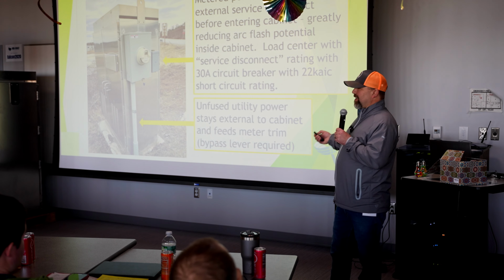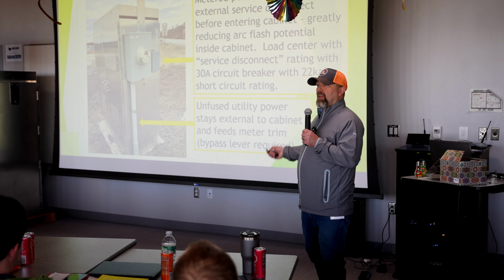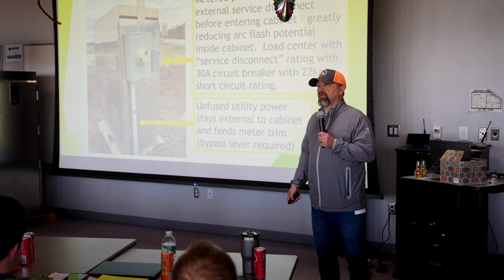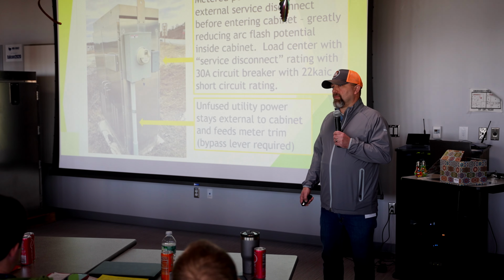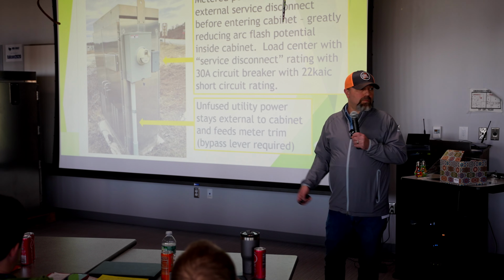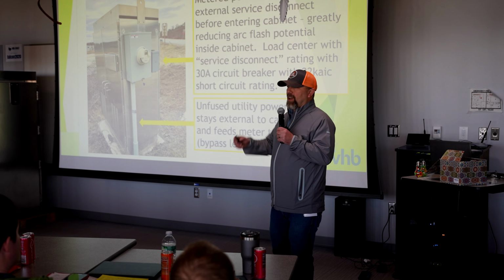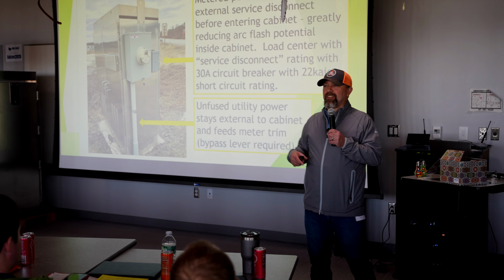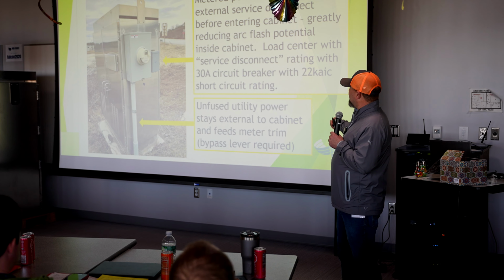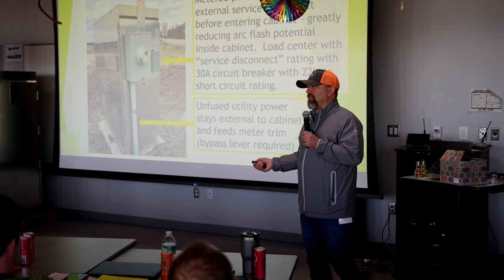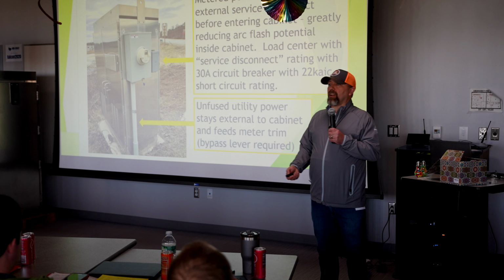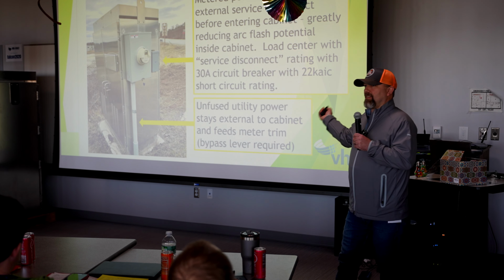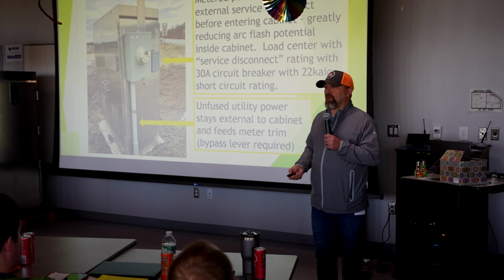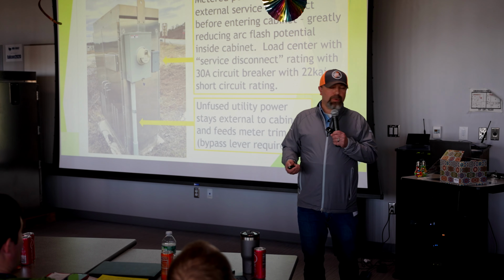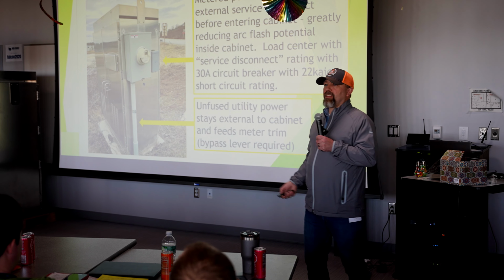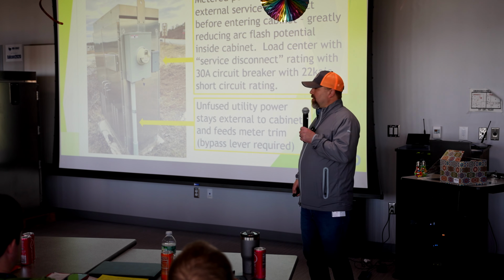I'm not looking for a shortcut for people, but 22 kAIC is probably going to take care of most of them, since most are going to be hooked to a 10 kVA transformer. So from what I'm hearing from the people that are smarter about this stuff than me, the 22 kAIC breaker is probably going to cover you in most cases. Due diligence should be done on it, so don't take this as, we should just put these in. Technically, you should be doing those calculations and contacting the utility company. But it sounds like this is at least a good faith effort to provide more protection.